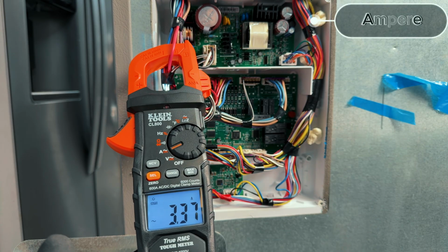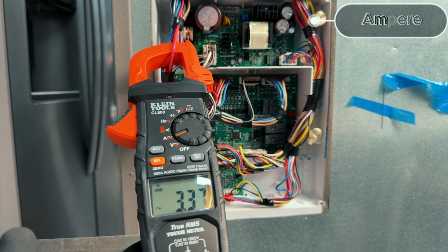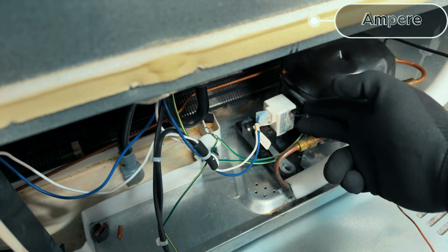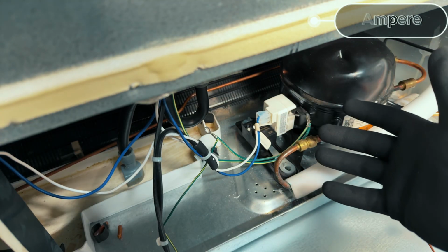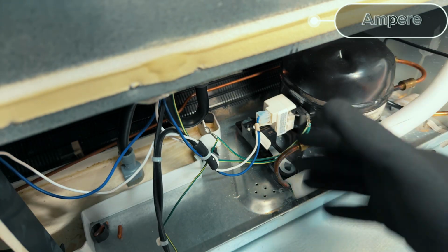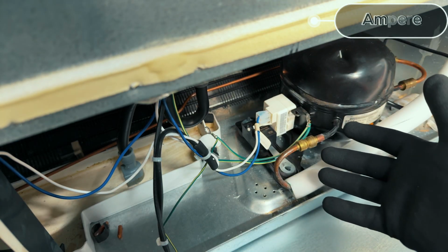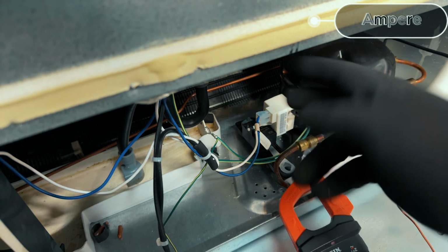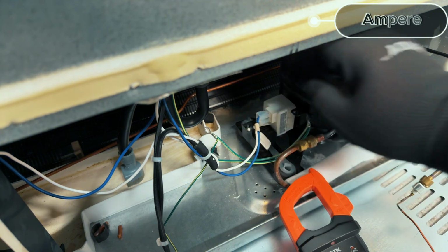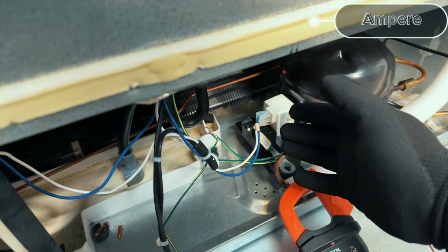Now let's go do the same thing on a compressor to show you how to check the amp draw on the compressor. All right. This is a pretty standard compressor with a start device. Keep in mind that variable speed compressors on inverters, you're not going to be able to check amp draw. They're variable speed, so compressors like that, you're checking for wattage. Amperage is not going to be something that you're going to be able to do. So if you see an inverter box, you're not going to be able to check the amperage. Check wattage instead. So of course, this unit here has got a start device. This is a single speed compressor, so we can check what the amp draw is on.